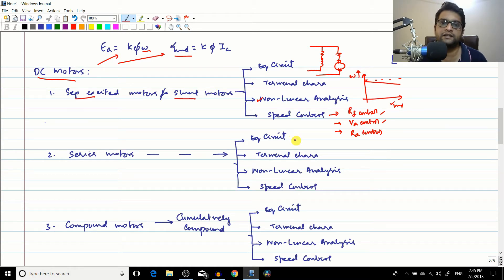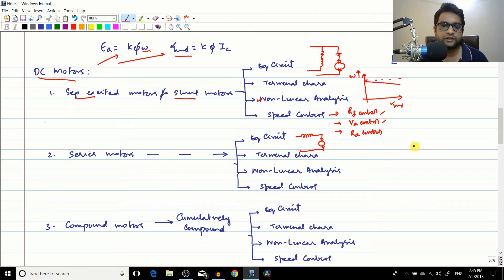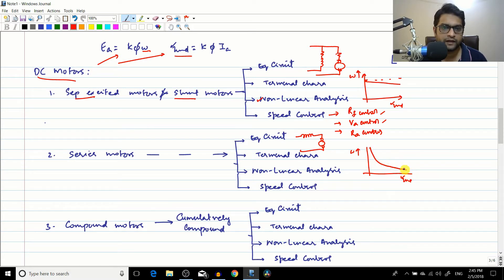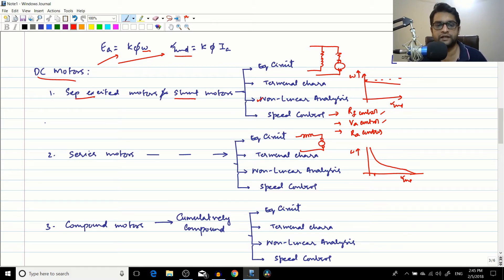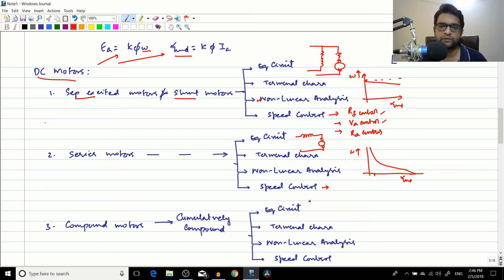In the series motor, the series winding and the armature are connected in series. The terminal characteristics were very interesting: the motor had a high starting torque, but under low load conditions — when the induced torque is small — the motor tends to reach a very high speed, going into an over-speed condition.